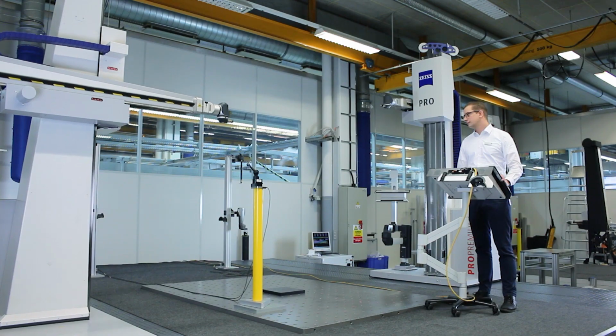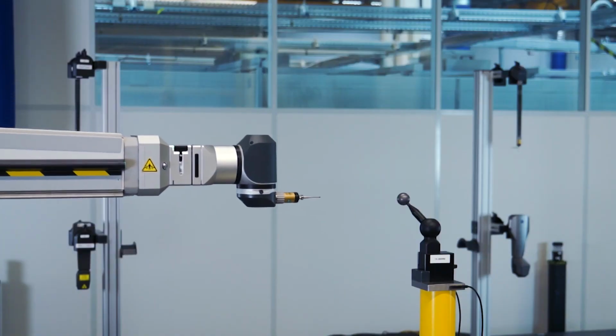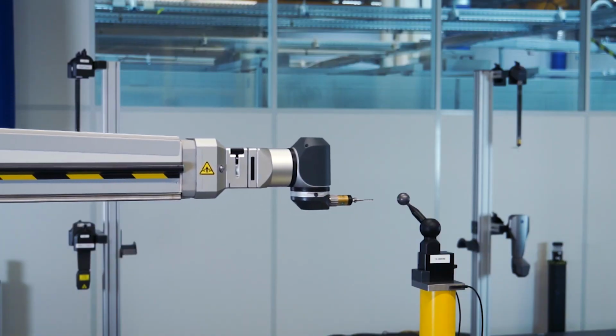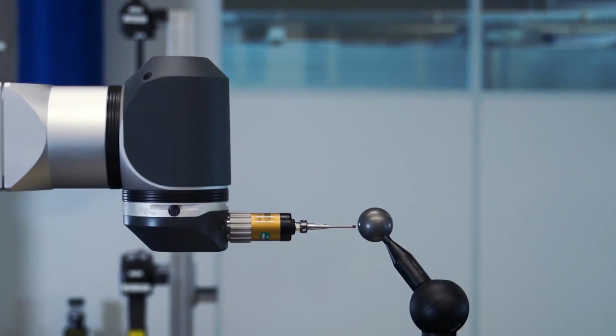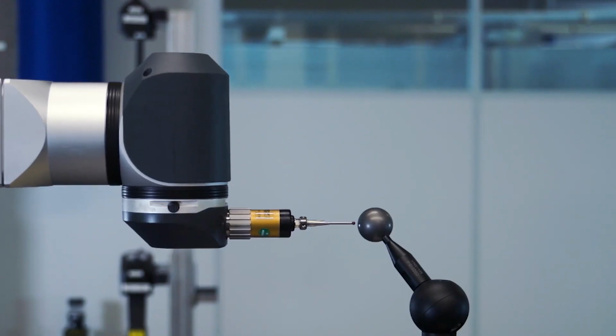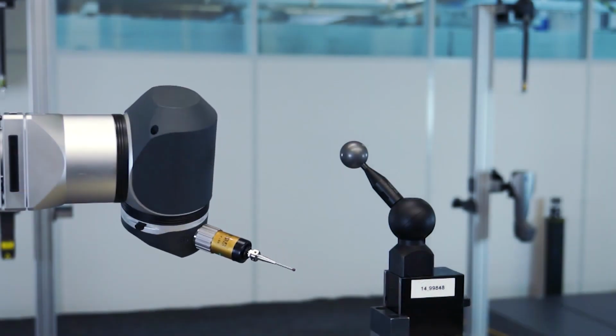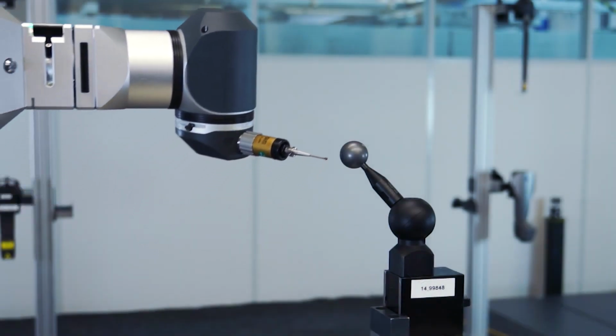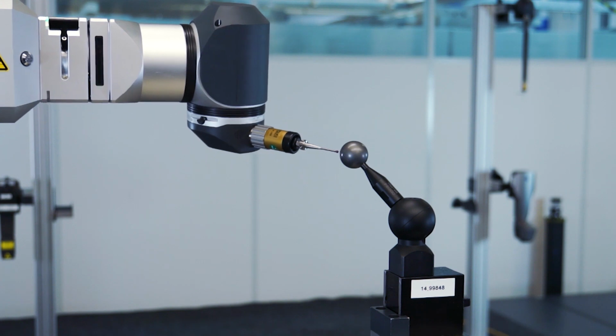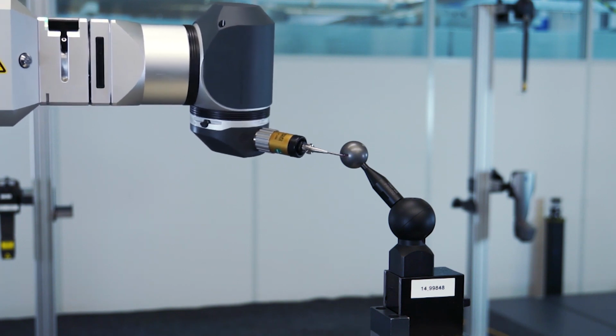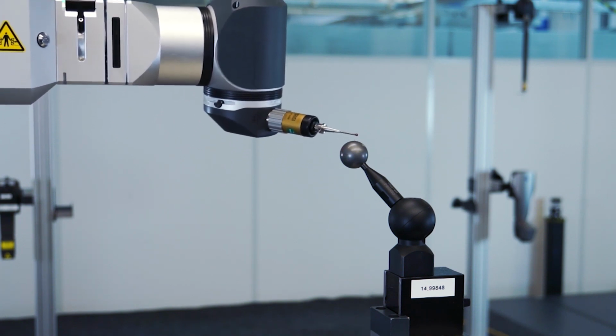As already mentioned, qualification must be carried out before the coupling. Please use the reference spheres belonging to the machine and also attach the temperature sensors, if available. These sensors should be positioned as close as possible to the reference sphere. When the qualification of both columns is completed, we can start with the coupling.